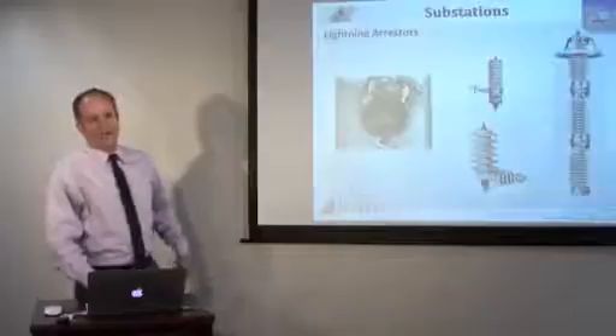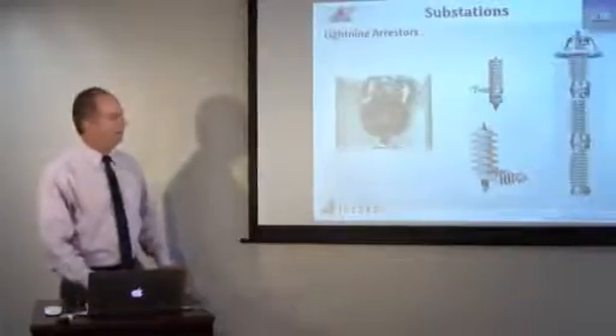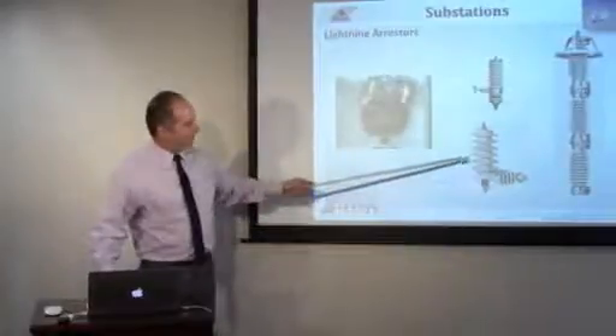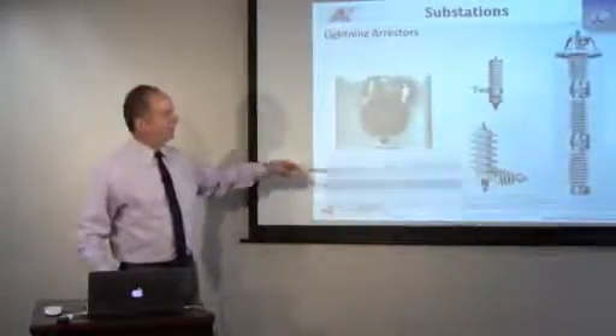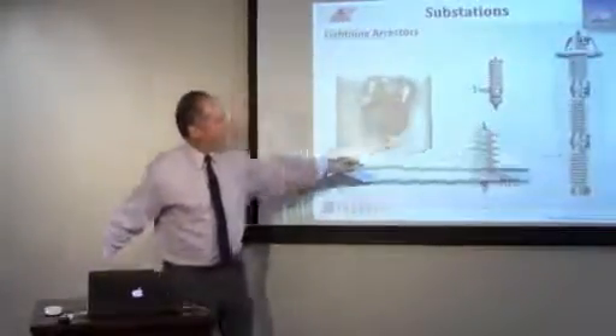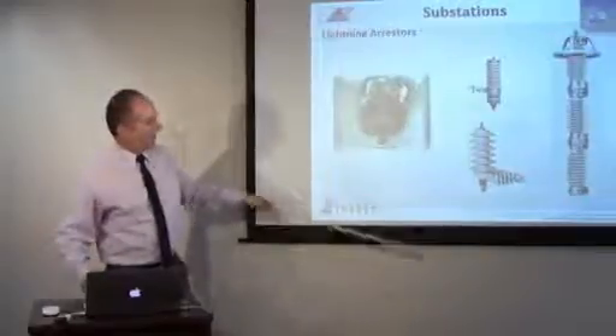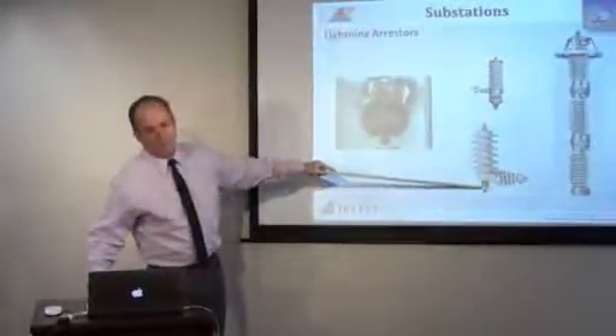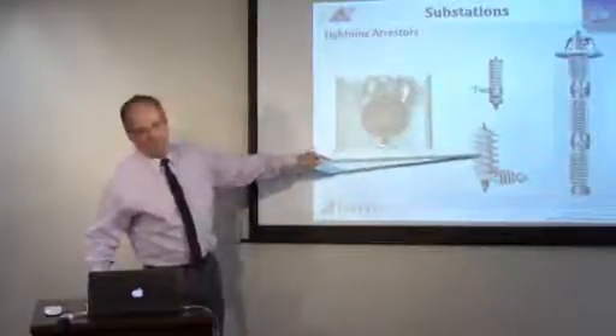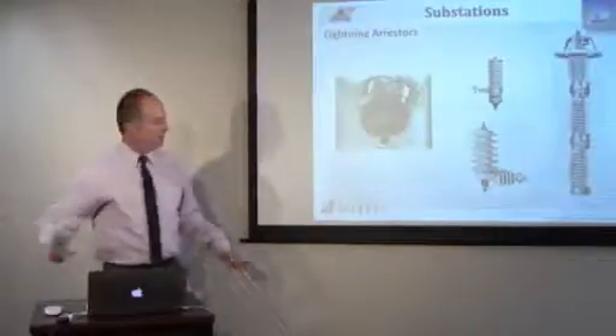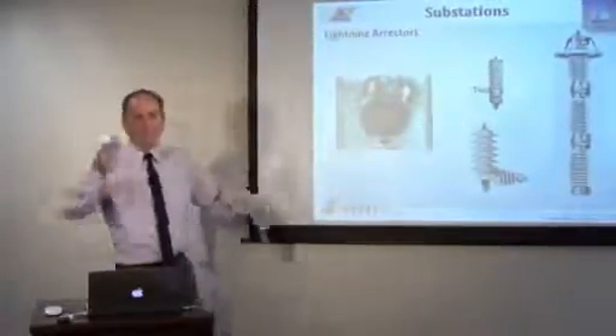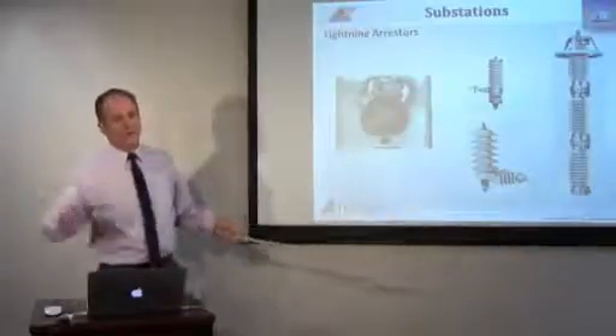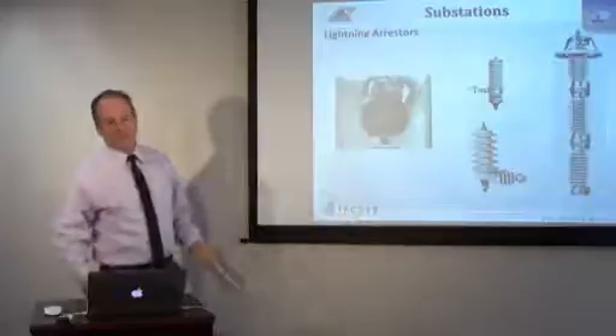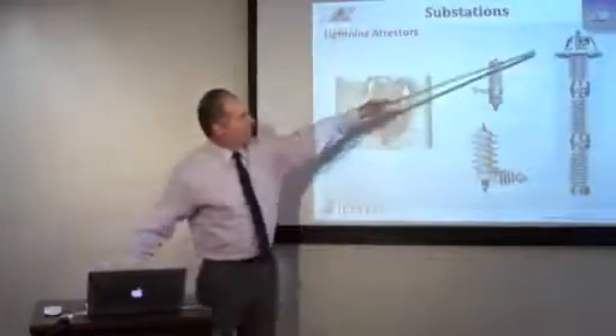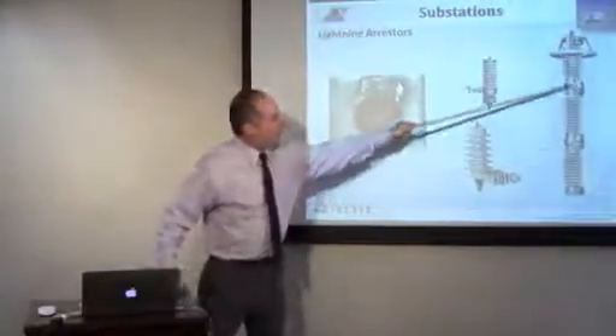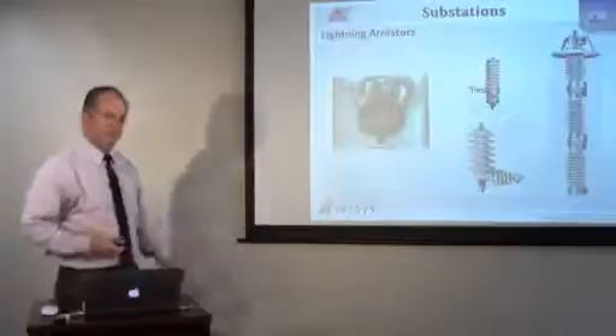But if the voltage gets too high, it'll limit so hard it'll still trip a breaker. But the metal oxide can handle a lot more energy. All these arrestors, whether it's on distribution or transmission, operate the same way. Here on distribution, you actually have a pressure relief plug on the bottom. If that arrestor takes on too much energy because a slow circuit breaker is not tripping, the bottom blows out of these things. Okay, so you can kind of see it hanging there. That's a bad arrestor. But if you have good coordination, these arrestors can go hundreds of thousands of times and still be operating good. The higher voltage ones operate the same pressure release, and they still try to limit and clamp voltages. It's just higher voltage.